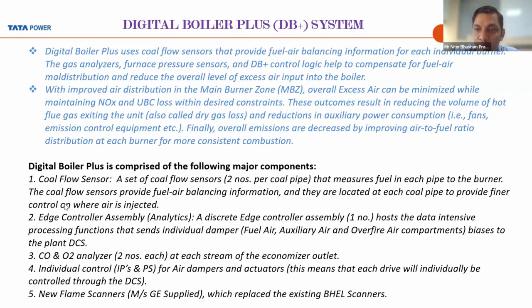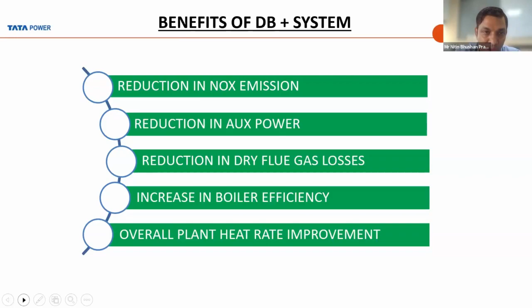Basically, the benefits of the DB+ system are that it directly helps in reduction of NOx emissions, and reduction in auxiliary power as the total air gets reduced. We also have a reduction in dry flue gas losses as the total air is decreased, a direct increase in boiler efficiency, and finally an overall plant heat rate improvement. Kindly move forward.